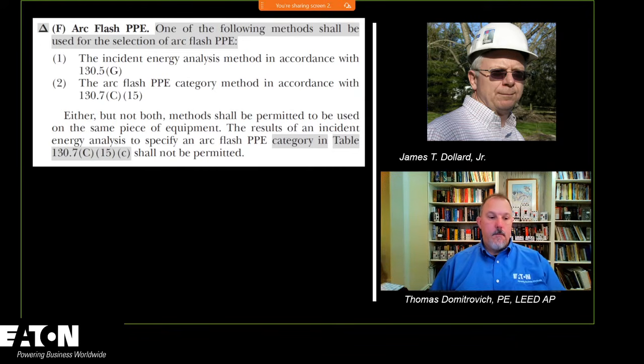What we need to understand is that arc flash risk assessment, without regard to the method you choose to apply, will never, ever be a perfect science. We all seek perfection in everything we do. I mean, we try to do the best we can. There's too many variables. When you get into 130.5 and you're doing an incident energy analysis, we tell you in 70E that it is an estimation. That's all it is.